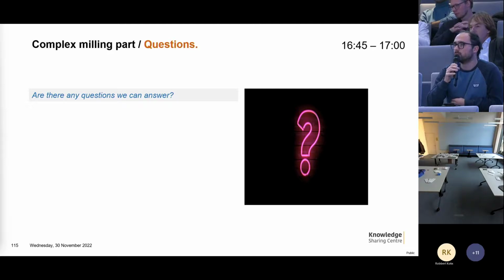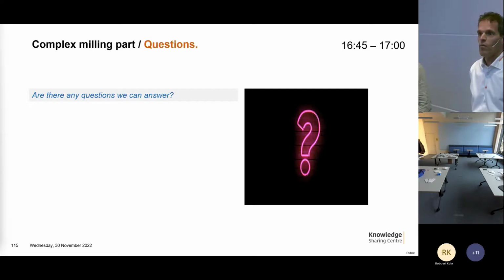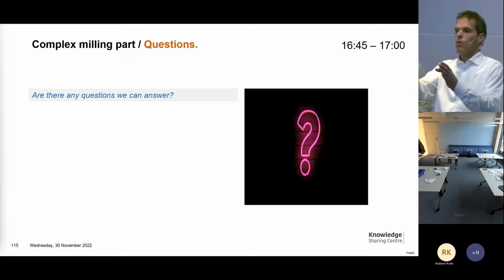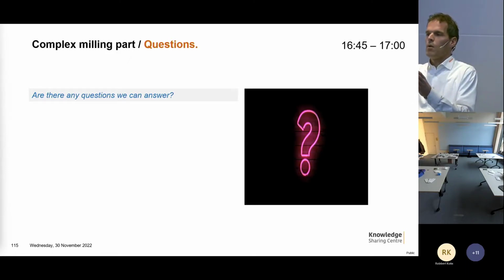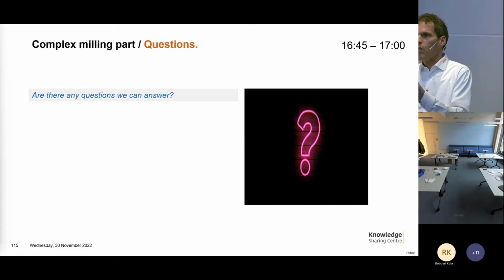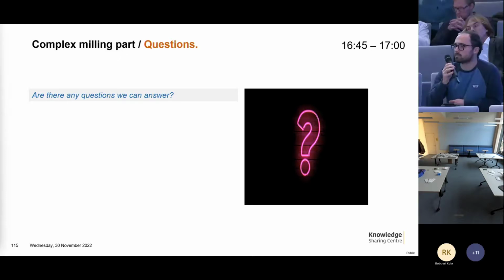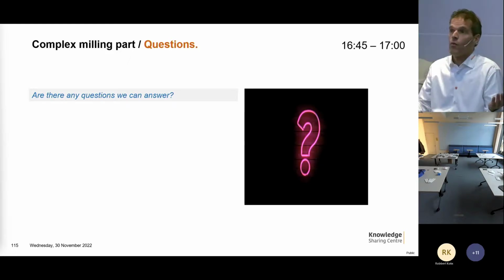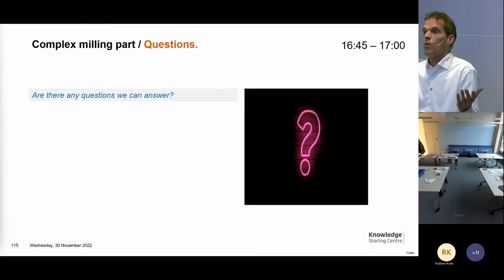So. Maybe one last question, then the most complex GD&T to measure is the profile one, profile of a surface, of a complex surface. Is that the most? No, in principle, we cannot measure all GD&T. Yeah, it's more like your bottleneck is most of the time your mechanical probe, so your probe sphere of at least 0.2 millimeters. So if you want to have like a thread, you have to go to a contour measuring instrument, as I showed in the movie clip, and for roughness to an even smaller radius, or white light interferometry if you do not want to contact. This is also a direction you can go.